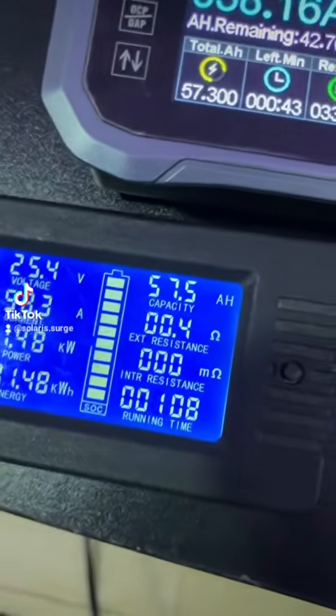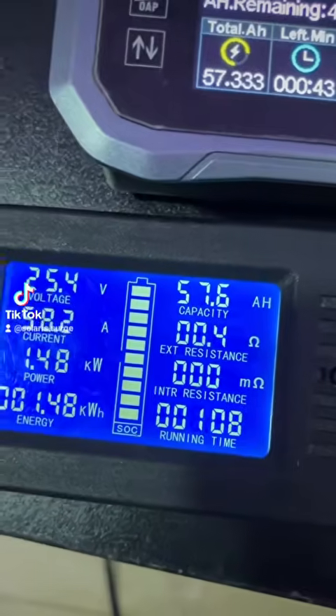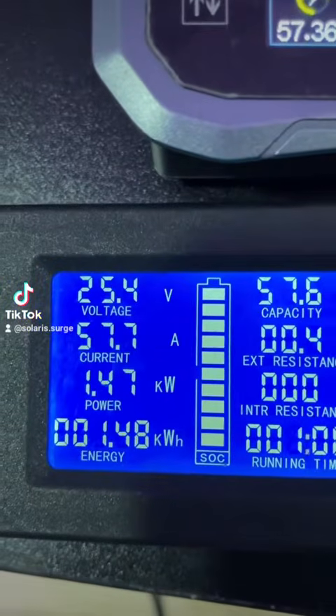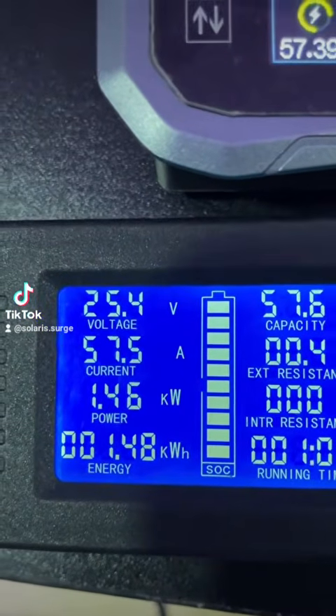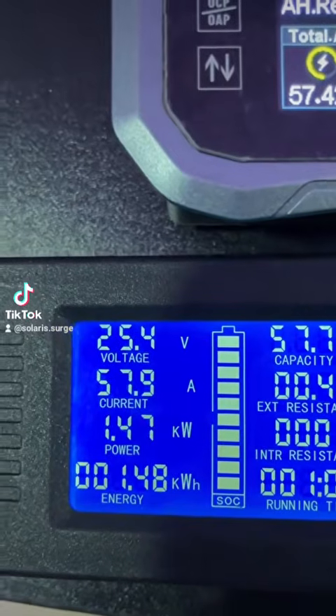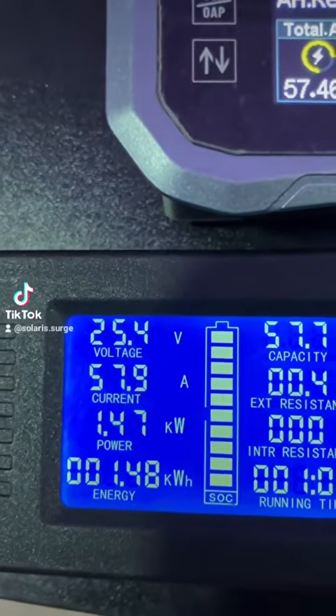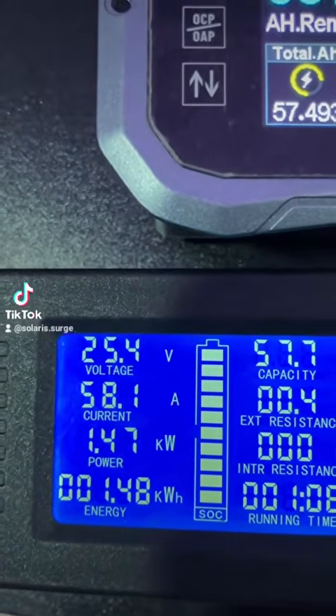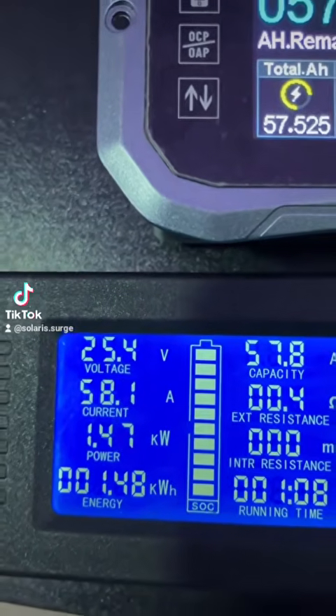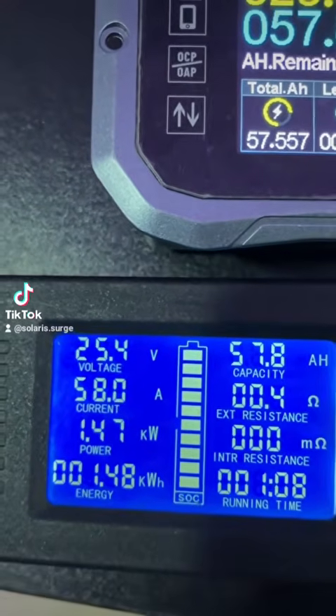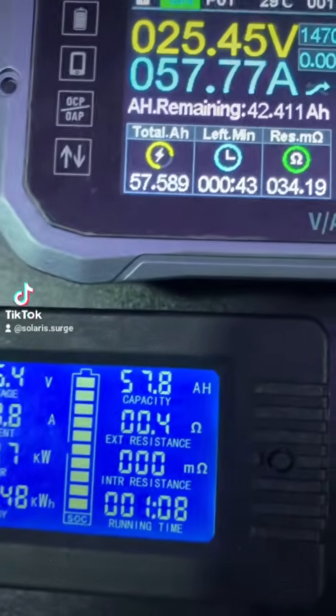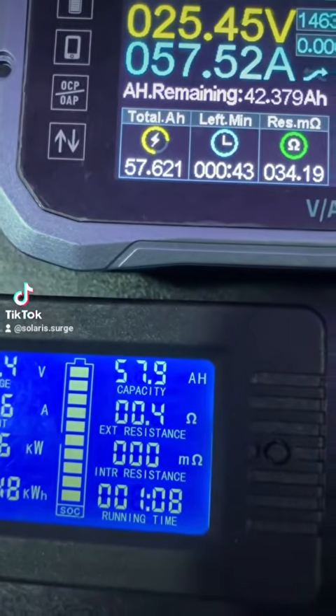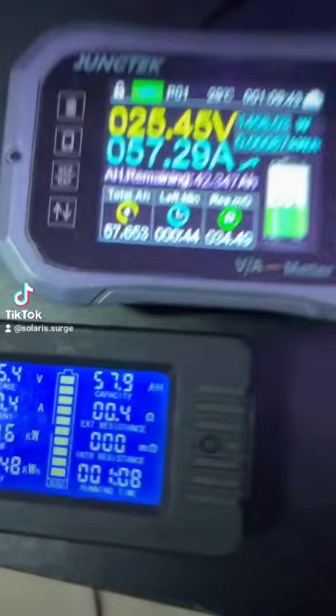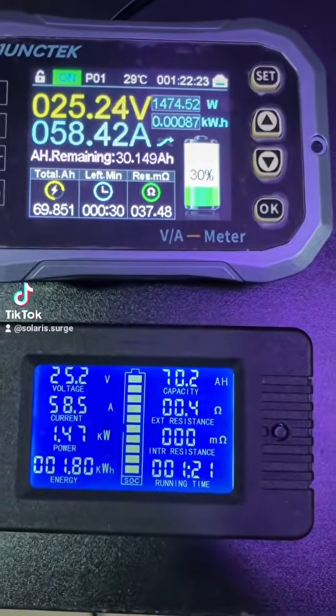After 1 hour 8 minutes we have drawn 1.48 kilowatt hours from the battery. 1.46 kilowatts is the power, 57.9 amps or 58 amps is the current draw. The battery voltage is at 25.4, and we have drawn 57.9 amp hours. So we have reached 70 amp hours now.